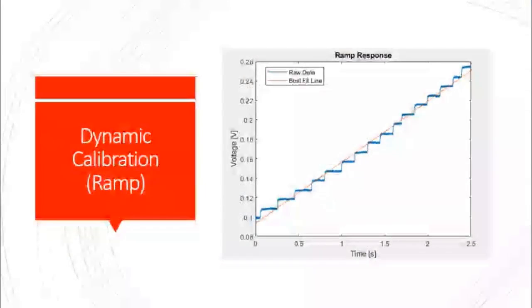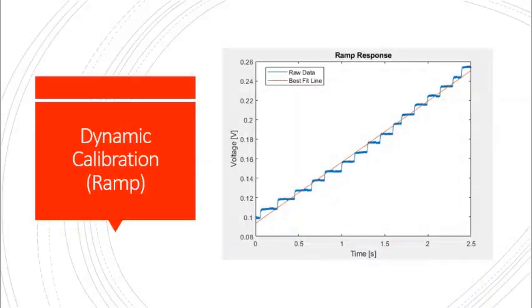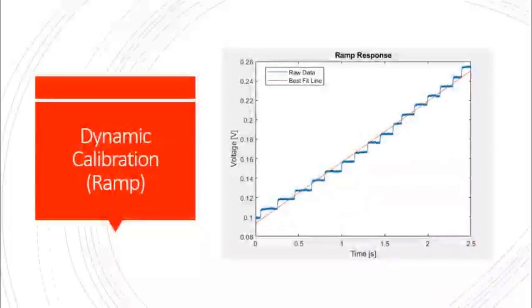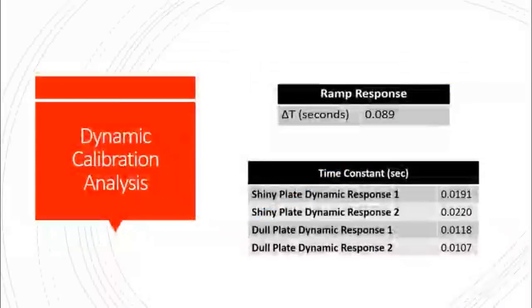We also performed a ramp response in which we moved the plate from in front of the sensor back at a constant rate. We found the linear relationship, and we also found the update time for the sensor based on the size of the staircase steps. Here are those values tabulated. The update time experimentally was 89 milliseconds, and given in the data sheet it was 50 milliseconds.